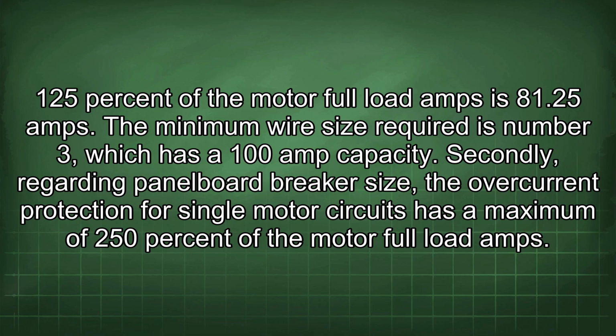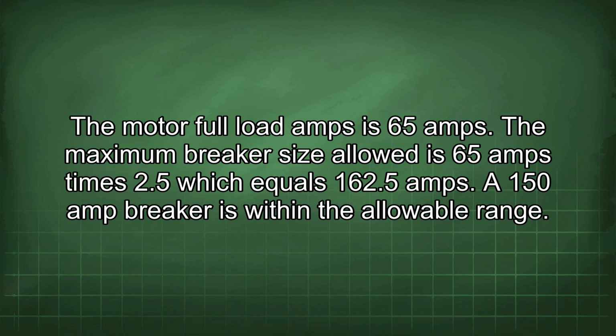Secondly, regarding panel board breaker size, the overcurrent protection for single motor circuits has a maximum of 250% of the motor full load amps. The motor full load amps is 65 amps. The maximum breaker size allowed is 65 amps times 2.5, which equals 162.5 amps. A 150 amp breaker is within the allowable range.